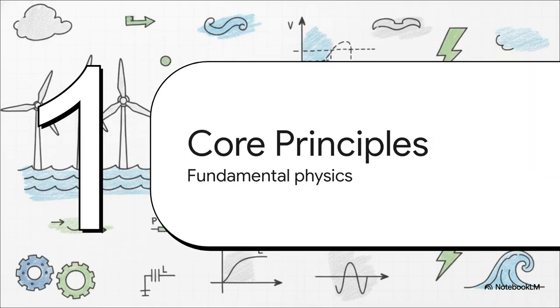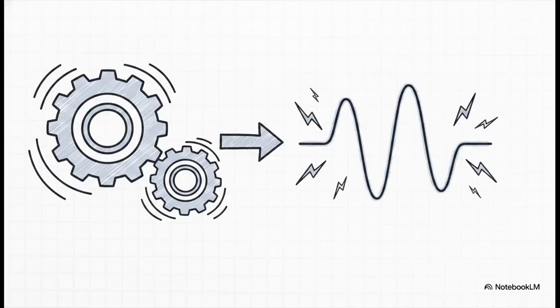All right, Section 1, Core Principles. Let's look at the fundamental physics. This equation right here physically represents exactly how mechanical rotation inside the rotor translates into electrical frequency on your grid. It's straightforward. Frequency, or F, equals the number of poles, P, multiplied by the speed in RPM, N, and then you divide all of that by 120. So if you've got a 4-pole machine spinning at exactly 1500 RPM, the math works out perfectly to a stable 50 Hz grid frequency. It's this elegant, totally fixed relationship that entirely dictates the mechanical design of your prime mover.